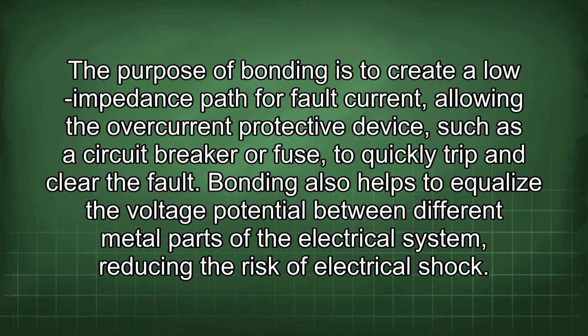The purpose of bonding is to create a low impedance path for fault current, allowing the overcurrent protective device, such as a circuit breaker or fuse, to quickly trip and clear the fault. Bonding also helps to equalize the voltage potential between different metal parts of the electrical system, reducing the risk of electrical shock.